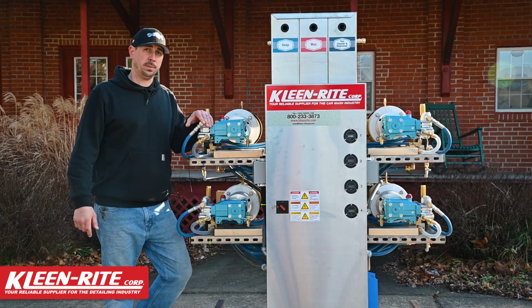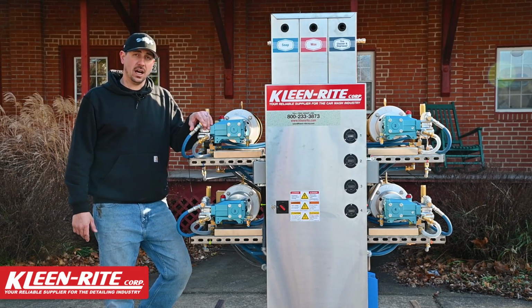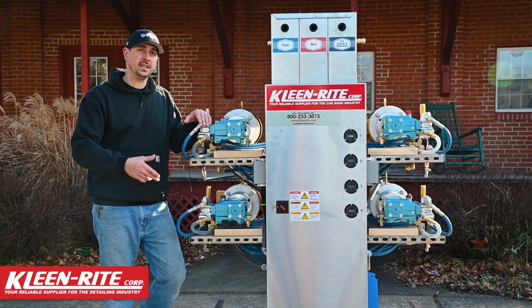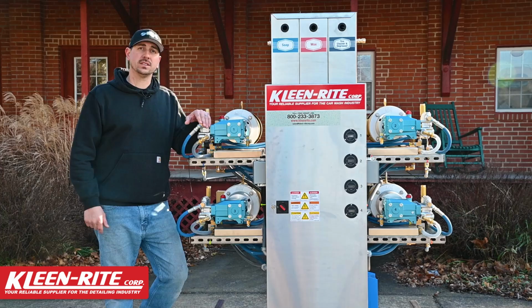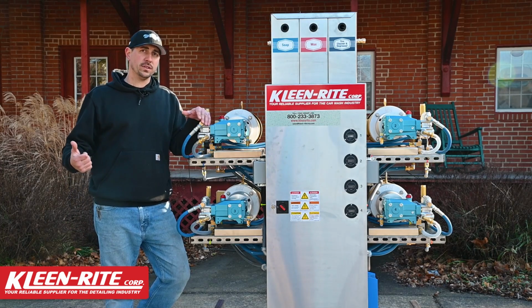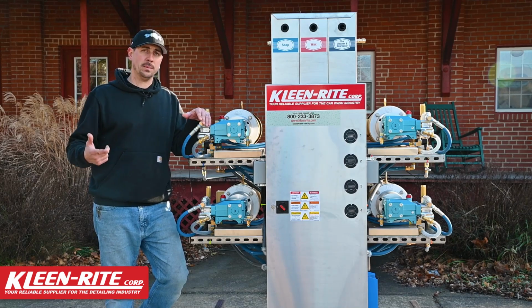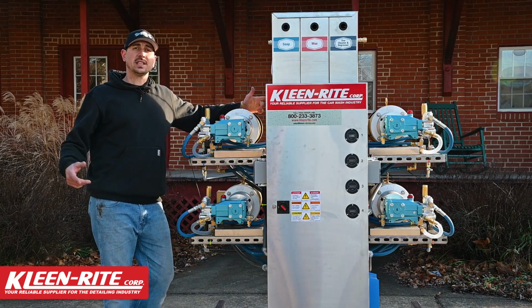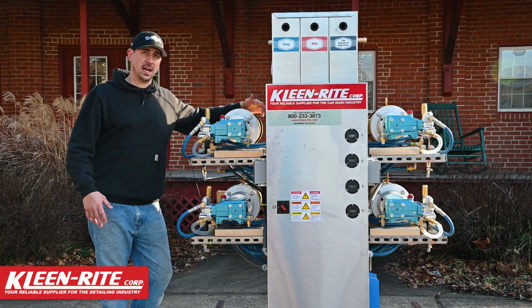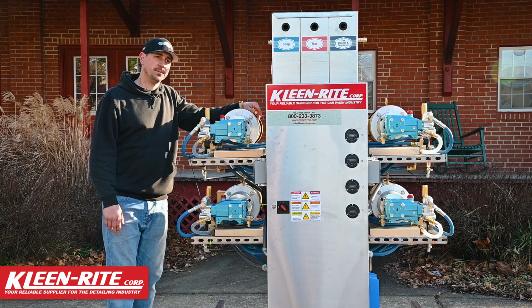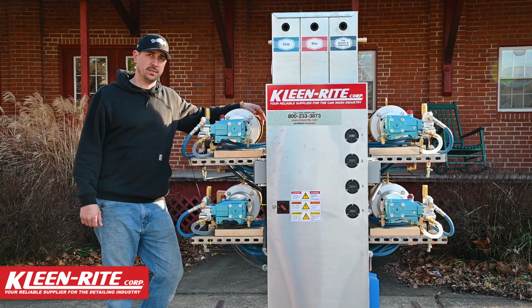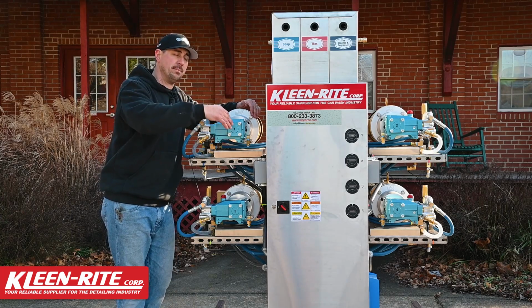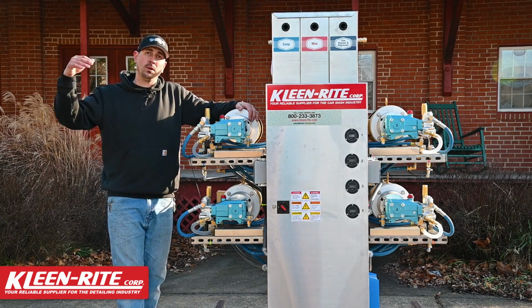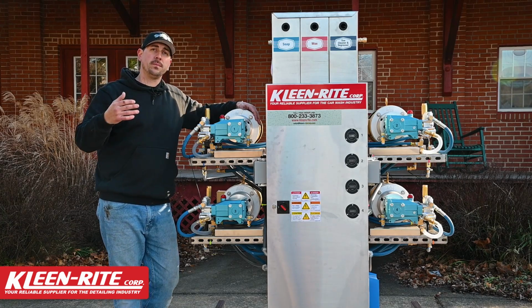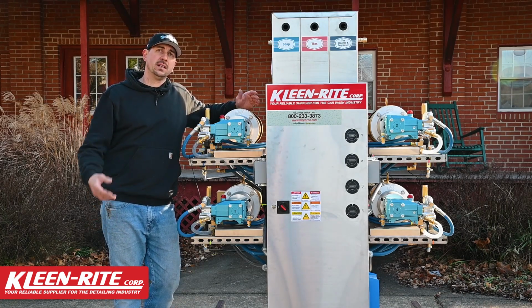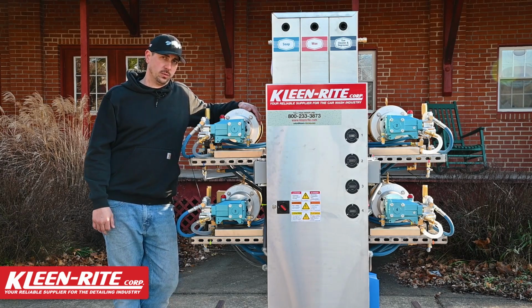All right, so let's talk about the footprint of the Operator Pro. Coming in at under 3 foot deep, 5 foot wide, and 6 foot tall, this guy fits through a standard man door. So no removing doors to get it in, and a ton of equipment room space saved. All right, so let's give a brief overview of why the pump stand is designed the way that it's designed, and an idea of how easy it is to install and service this unit. We're pulling one set of main power wires in, and we're only pulling one hose or hard pipe, however you decide to do that, to supply the feed water to this unit as well.